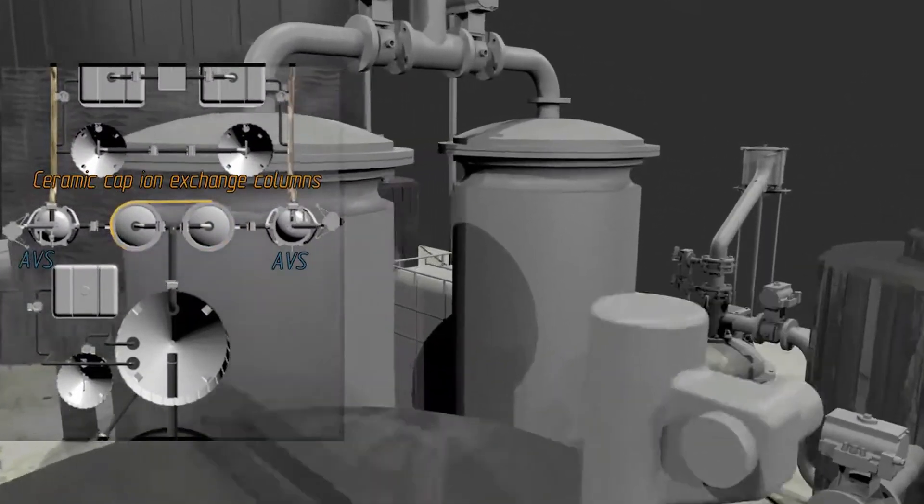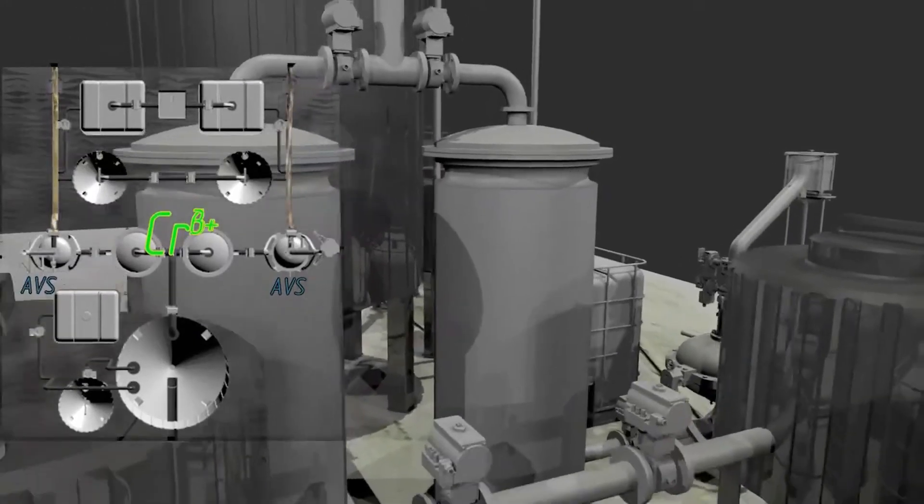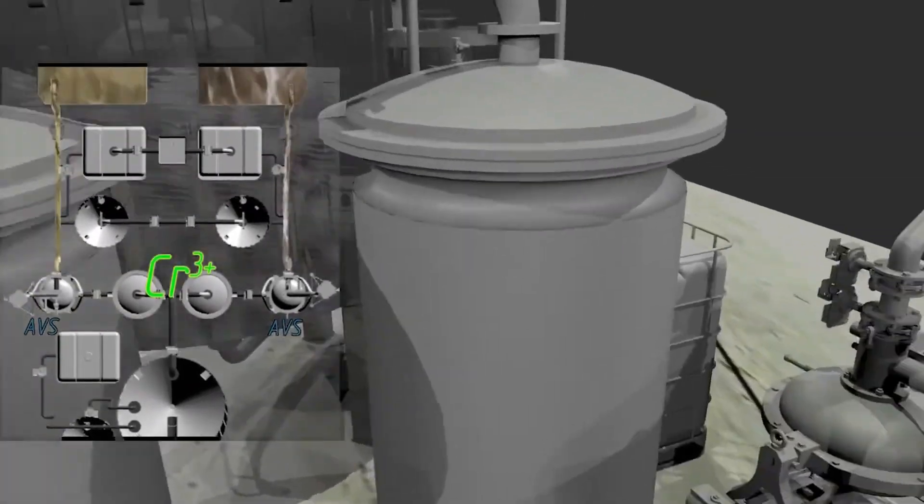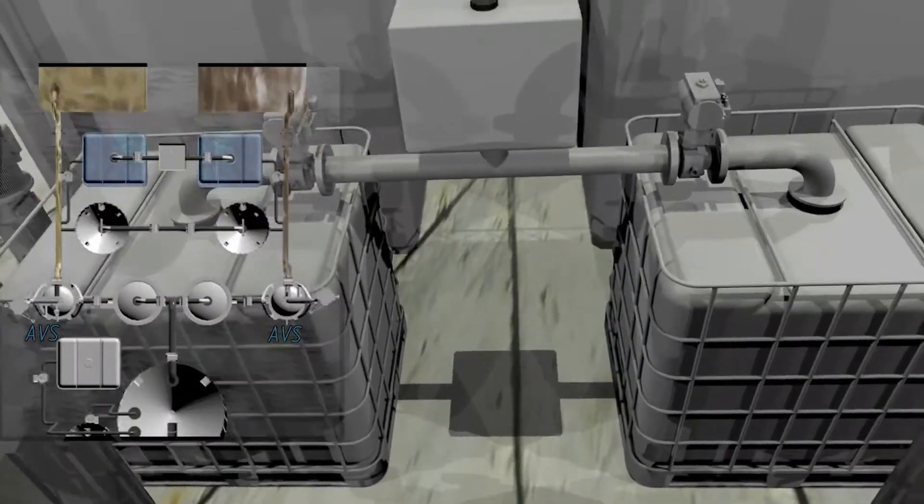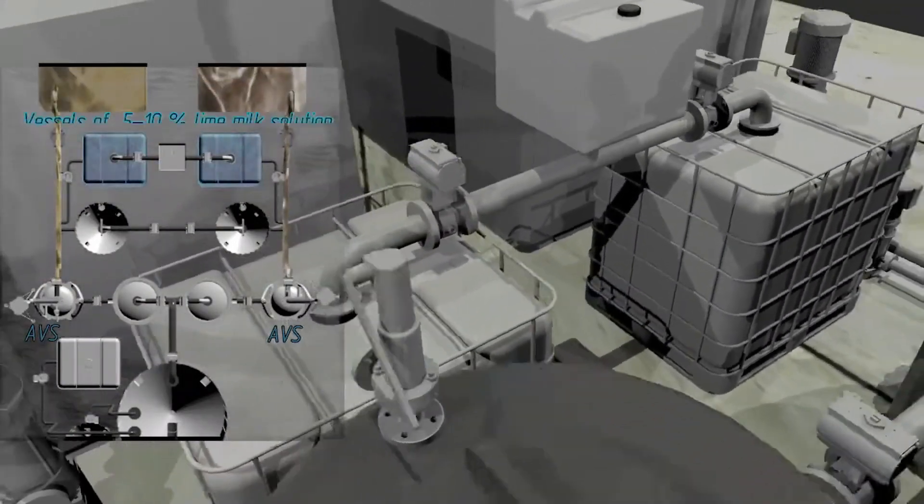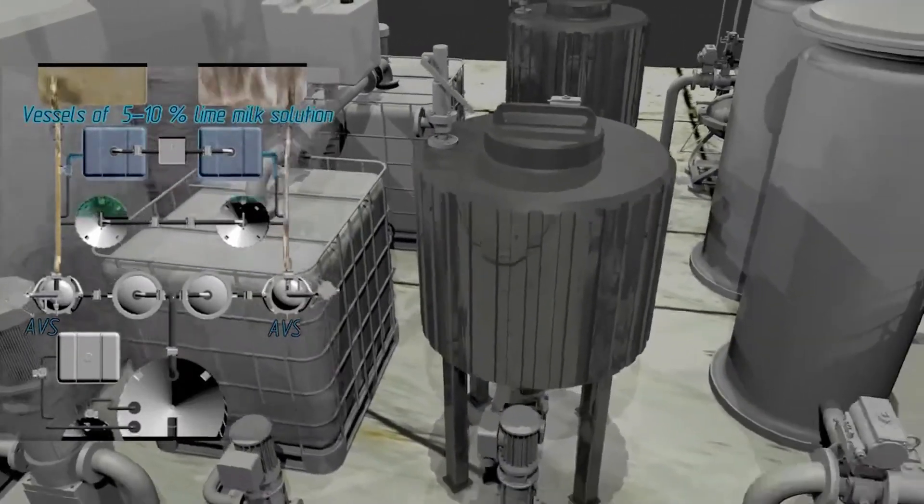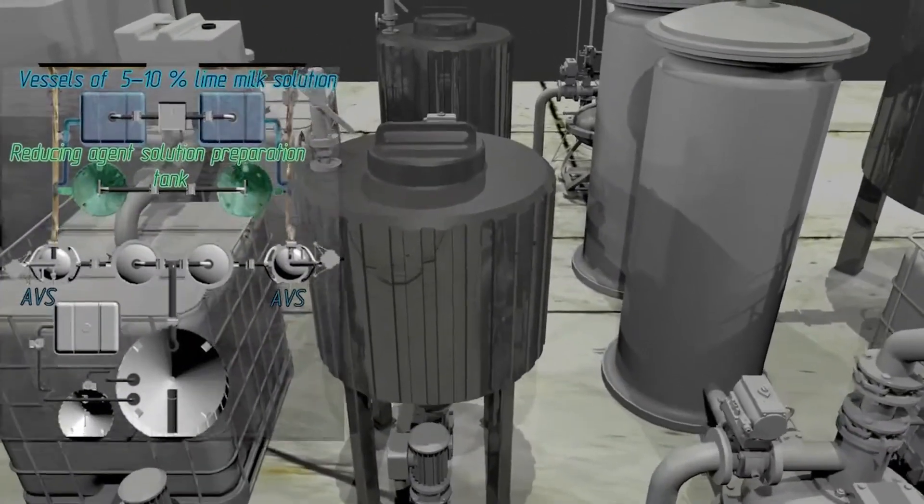Mass exchanging columns are installed near these devices to improve the conditions for simultaneous reduction of hexavalent chromium to trivalent chromium, as well as for formation of heavy metal hydroxides. A lime milk solution from one tank and a reducing agent process solution from the other tank are supplied to AVS devices concurrently with treated wastewater. After treatment by means of AVS, the wastewater enters the sump for clarification.